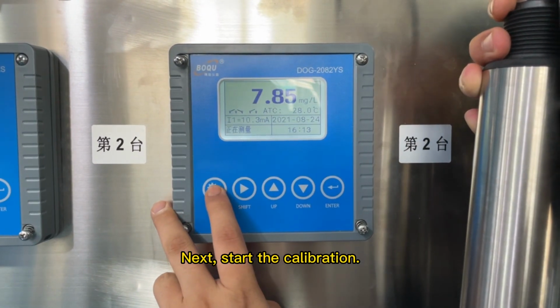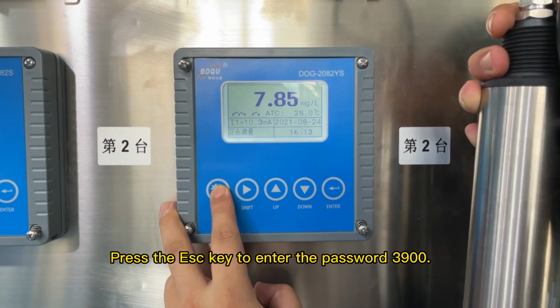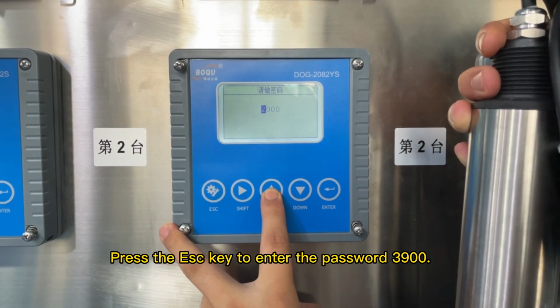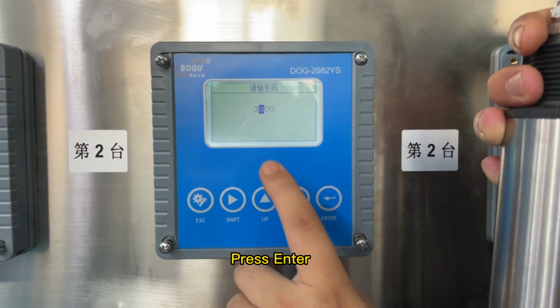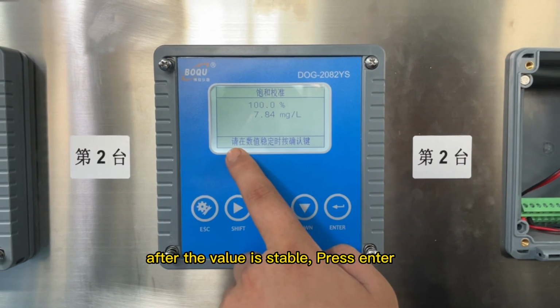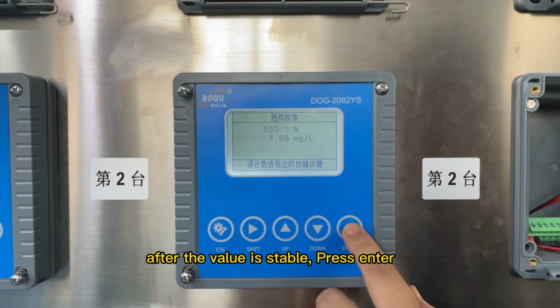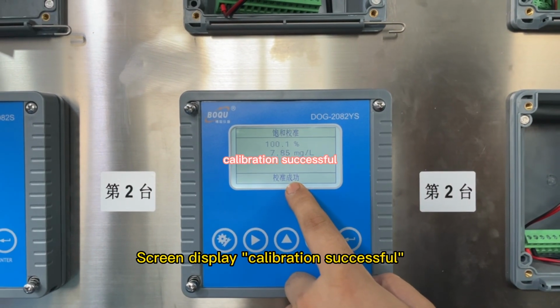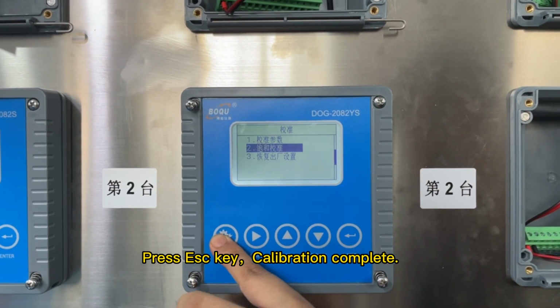Next, start the calibration. Press the ESC key to enter the password 3900. Press Enter. Press the up and down keys to select saturation calibration. Press Enter. Wait 3 to 5 minutes. After the value is stable, press Enter. Screen display calibration successful. Press ESC key.